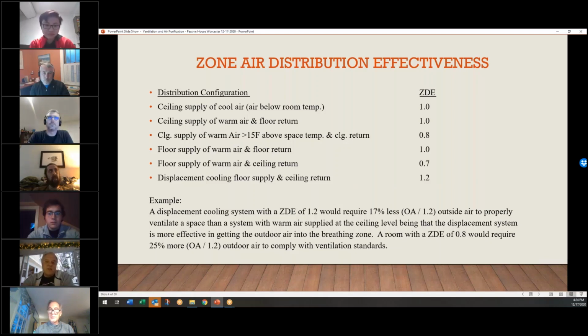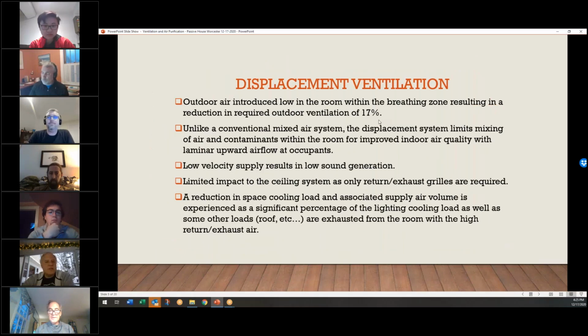On the same vein, if you have a displacement system where you bring cool air in at the floor and exhaust it high, you can actually take a credit. You can reduce your amount of outside air because you're bringing the outside air in where the people are, right at their level, so it's more effective ventilation. If you're a mechanical engineer, you might want to keep this in the back of your head: what are my temperatures, and how am I distributing to the space, because it may mean that I need more outside air. So that's why I brought that up. If you go to the next slide, I think it's just the next one.